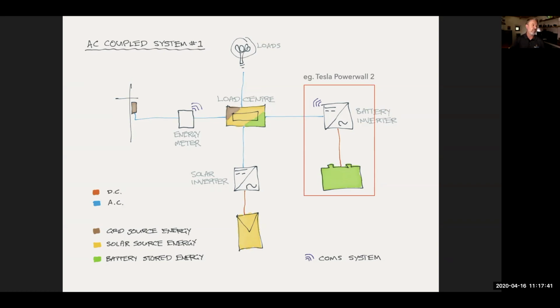They're wanting to add battery storage, so a Powerwall, and I put a red box around it to indicate that's one piece of equipment. What we'd call a BESS, a battery energy storage system, can be just coupled via the blue lines, which is AC, into the existing installation. A critical part of that is the energy meter with a little transmitter shown there. It's not actually a transmitter in practice, it's a dedicated cable, and its purpose—it's not the utility's meter, it's the meter that comes with the AC coupled storage solution—is to allow it to see the exchange of energy occurring at the point of connection with the grid.